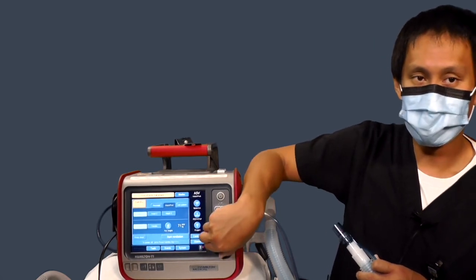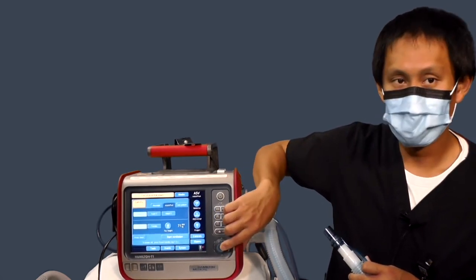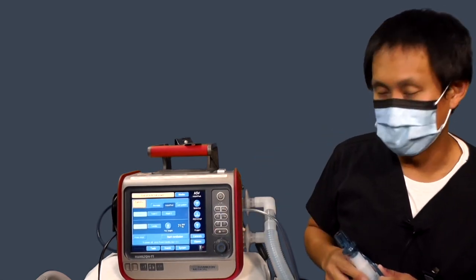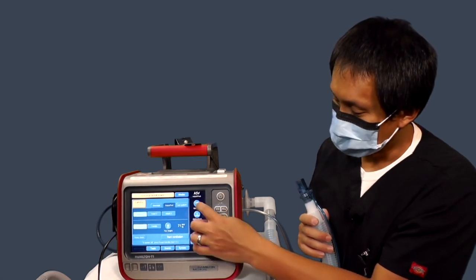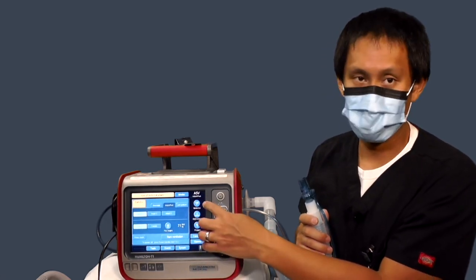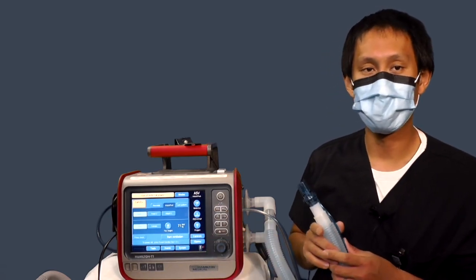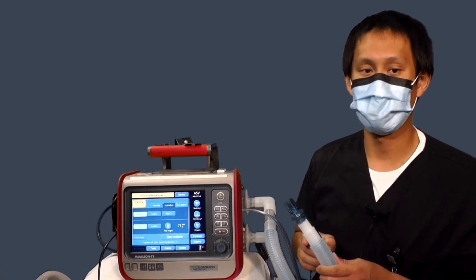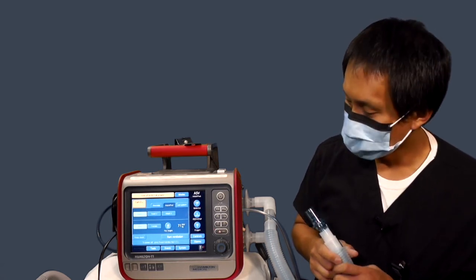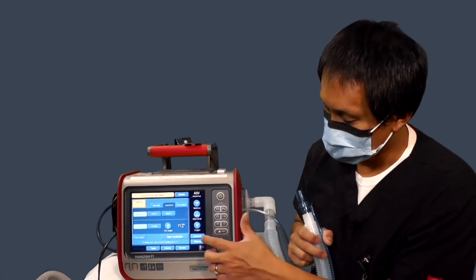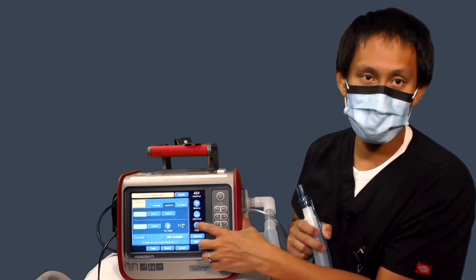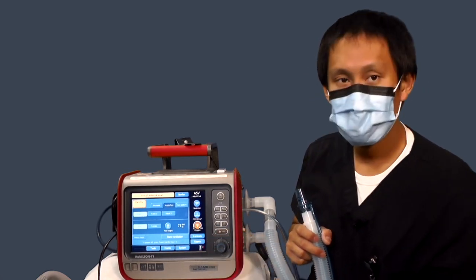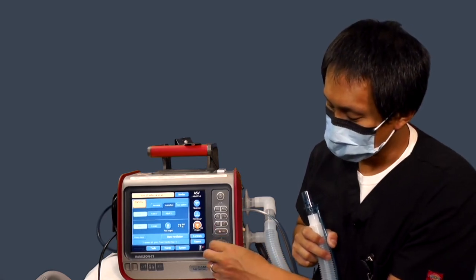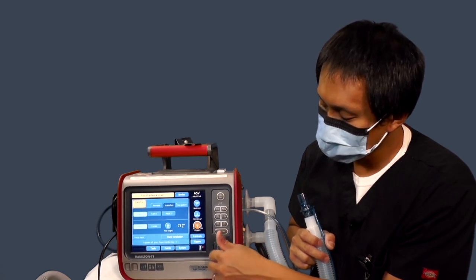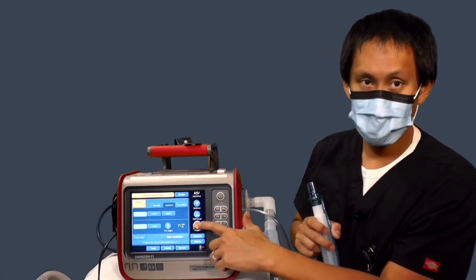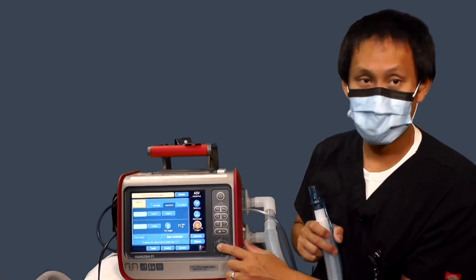This is a rotary knob, so it twists and turns and also clicks. So when you're making changes, you can confirm with the knob or on the screen. This is a double confirmation ventilator. By that I mean to make every change, you have to confirm your change twice. For example, if I want to change the oxygen percentage on this vent, I click the oxygen icon on the screen. It'll go from blue to orange. Make my adjustment. For this, I'm going to turn it down to 21%. You can hit the screen again and it'll confirm your change, or you can tap the knob and it'll confirm the change.